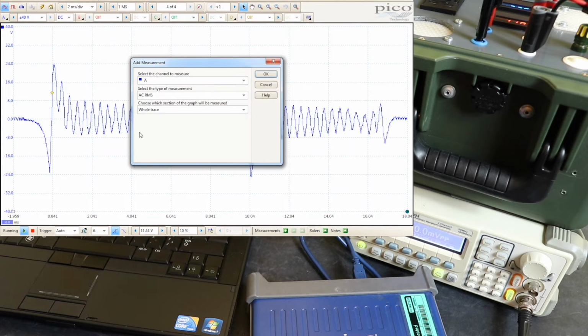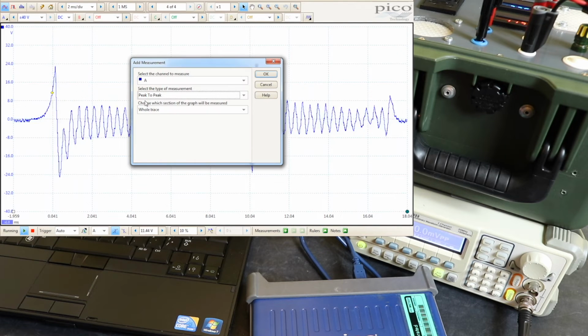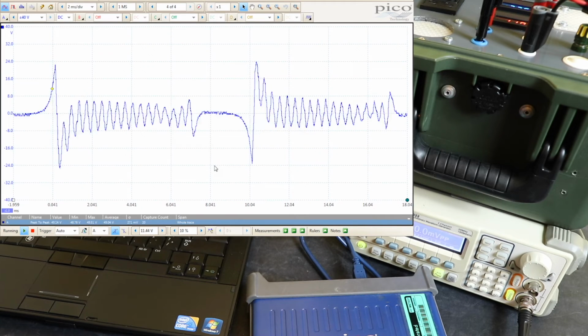What I like to do when I'm measuring these signals is measure the peak-to-peak voltage and plot that against the generator output and the field voltage and field current of the generator as well, so I can see how the signal is doing, and also I can look to see if there's any noise on the signal, if there's any degradation in the actual signal.